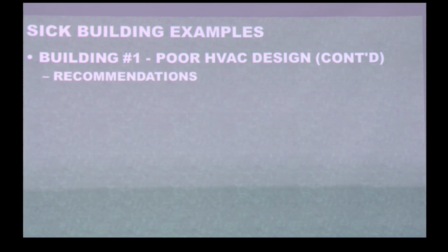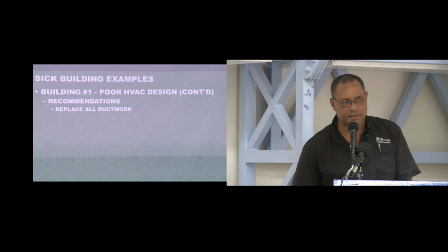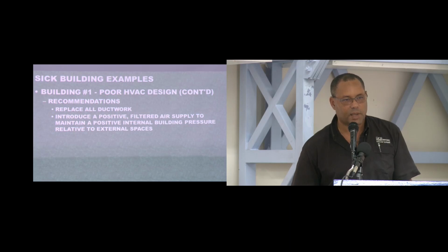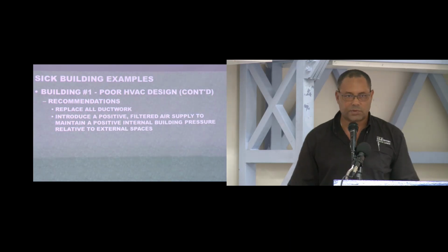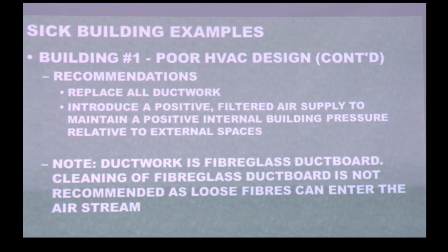So before you do an industrial clean, you might want to change your ductwork. There's nothing you can clean outside of that ductwork that's going to save you. You also have to change the way your building operates. You can't have it sucking air from anywhere. You have to introduce filtered air and make sure the building internal pressure is positive. If you've got people walking in off the street, every time they open the door, the air must go out, not come in, or you end up with the same problem. Just to note that the ductwork image that you saw there was fiberglass ductwork, so cleaning it is not recommended. You clean it, you're going to rip the internal surfaces of the ductwork, and you can get loose fibers of fiberglass flying all over people's desks. Not recommended.